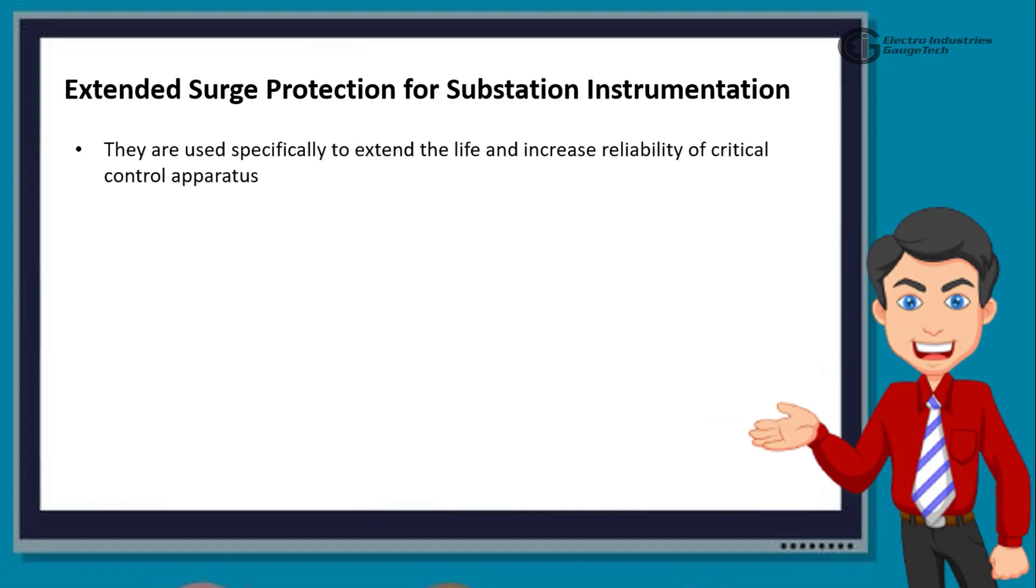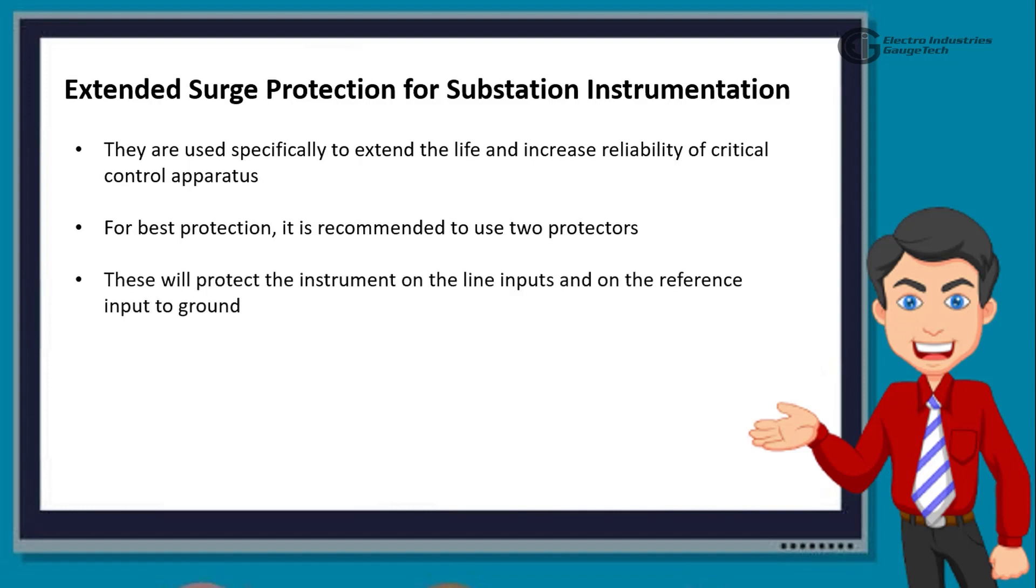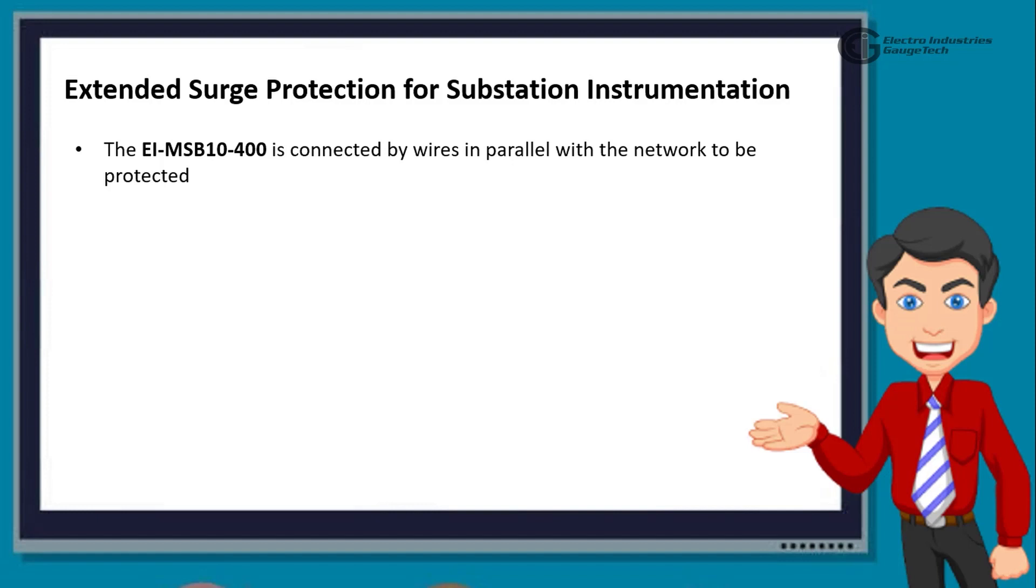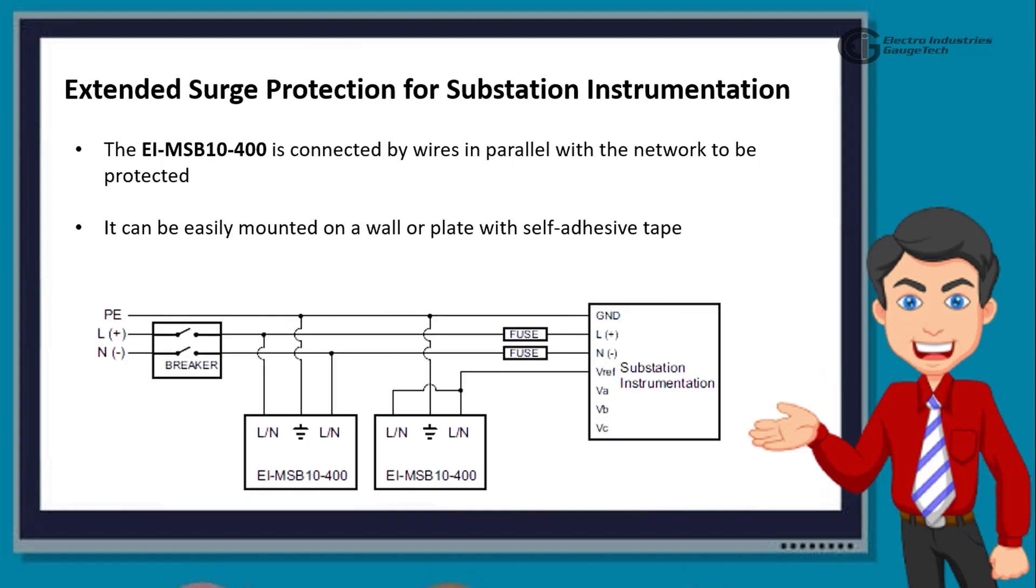They are used specifically to extend the life and increase reliability of critical control apparatus. For best protection, it is recommended to use two protectors. These will protect the instrument on the line inputs and on the reference input to ground. The protectors have LED indication to enunciate when the protection has worn out. The EI-MSB10-400 is connected by wires in parallel with the network to be protected. It can be easily mounted on a wall or plate with self-adhesive tape. The image here shows the wiring schematic for extended surge suppression suitable for substation instrumentation.